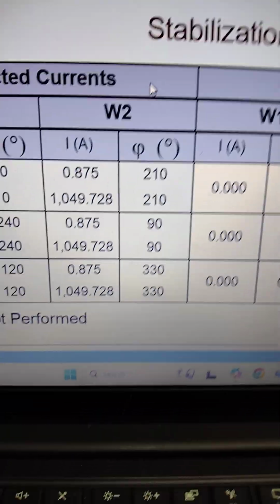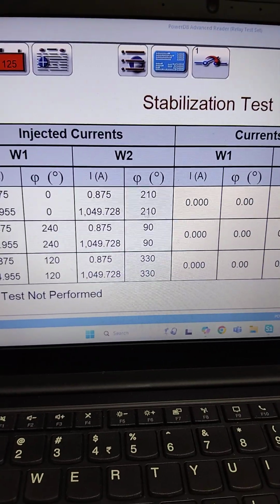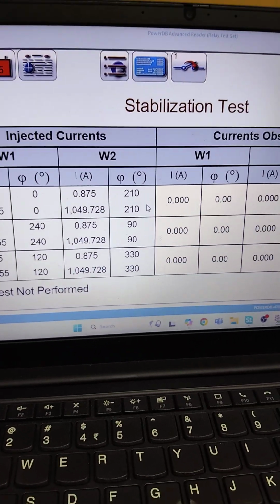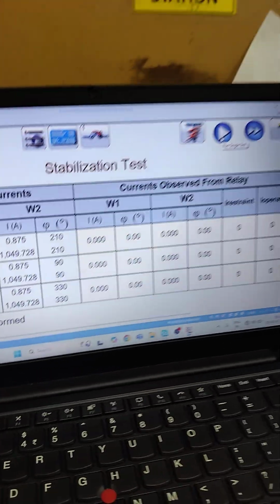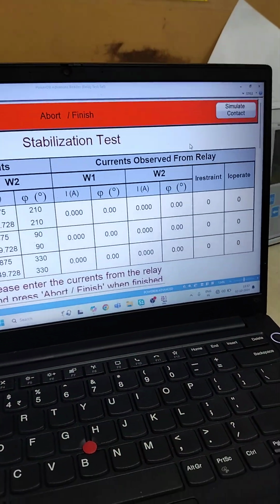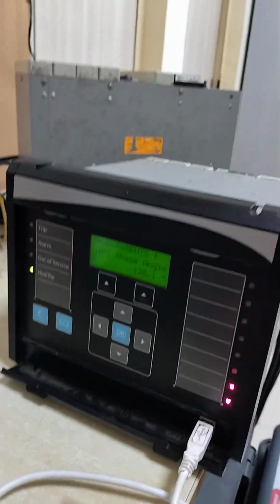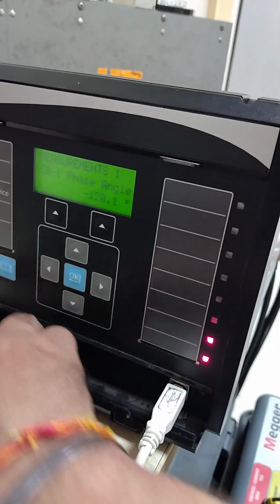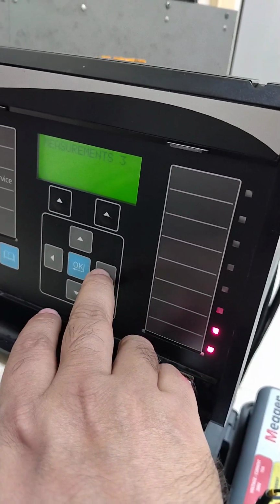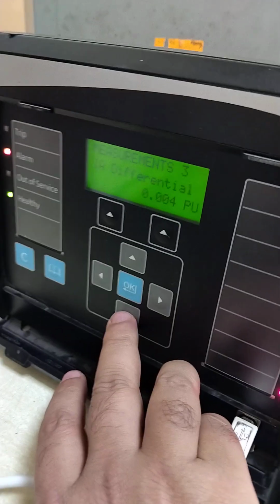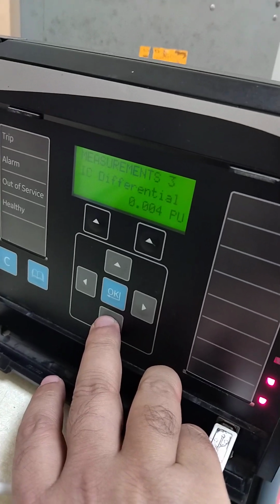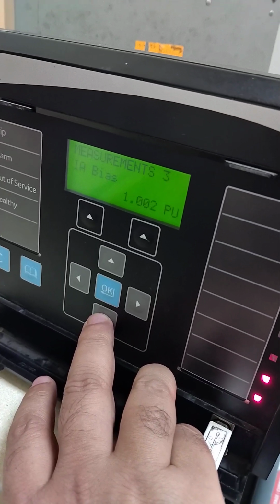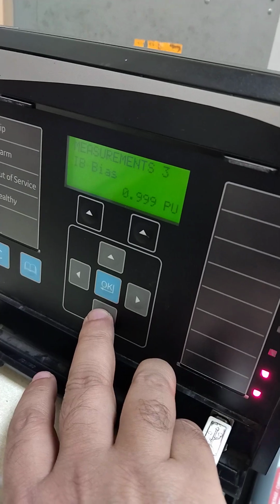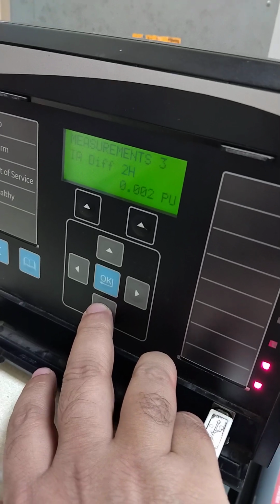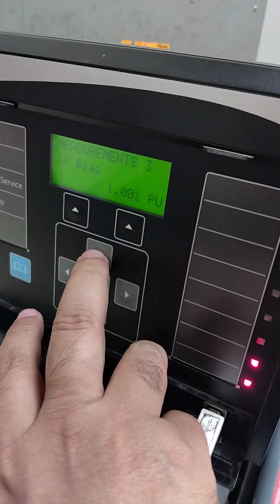So now you can see it's 210, so the angle shift is 0 and 210. So now we'll just enable it, and once you enable it, you can see in the device HMI, in the measurement 3 tab, the differential current on phase A, B, C is almost 0, but the biasing current is almost 1 pu. So this is what we are testing here, the stability criteria.